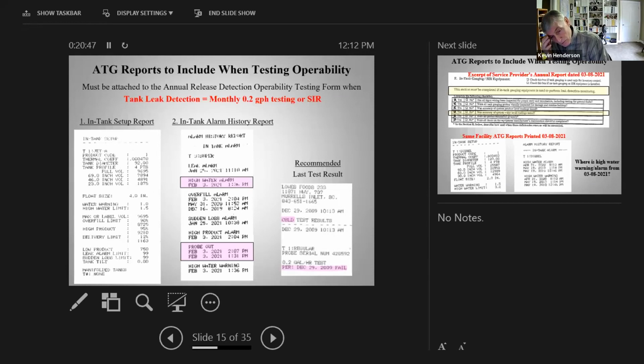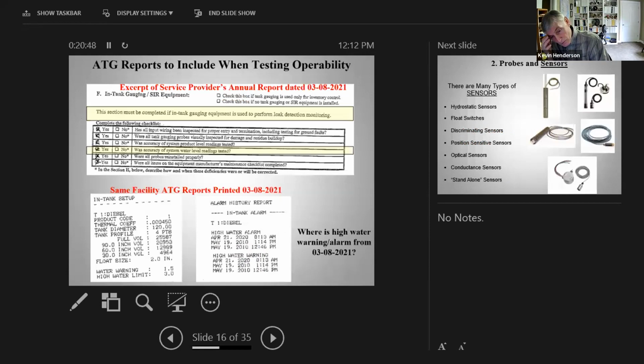This is an example of what is very commonly seen. The top part of this is an excerpt of some tester's form. And you'll see they got this correct. This section must be completed if in-tank gauging equipment is used to perform leak detection monitoring, meaning they're doing 0.2 testing. And then if you look at the other highlighted question there, the fourth one down, was accuracy of system water level reading tested? And he indicated yes. He checked the little box yes. It's easy to just check boxes on a form. We always want to back that up if we can.